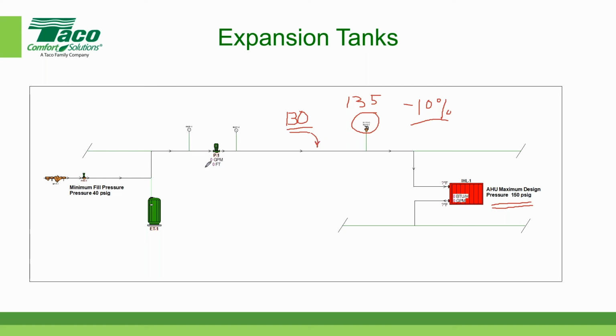Well, let's assume that the pump has the ability to add the delta P of 20 pounds in the system. So if I wanted to have a maximum in the piping system of 130, then I wanted my suction pressure to be 130 minus 20 if the pump delta P is 20. So my pressure on the suction side of the pump wants to be 110. And that's also the pressure I want to have for my maximum pressure for my expansion tank. And the reason that these are the same two numbers is because the expansion tank needs to be connected to the suction side of the pump. And that connection point is called the point of no pressure change.